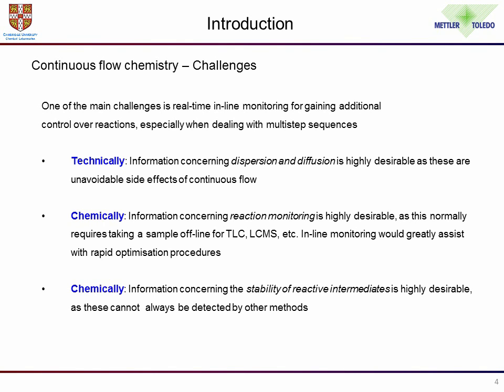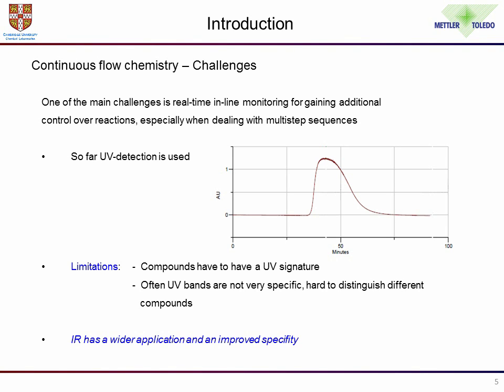There are significant challenges with the techniques we have today. For example, if we were to use UV monitoring — pretty well the only detection technique currently available for inline monitoring — there are significant problems and limitations. Not all compounds have a UV signature we can make use of, and often the UV bands are not terribly specific. If you have mixtures of compounds, it becomes very difficult to distinguish between them without diode array or further analysis. Infrared spectroscopy has, in principle, much wider application and very much improved specificity, providing this additional structural information which we can deconvolute by various computational or manipulative methods.